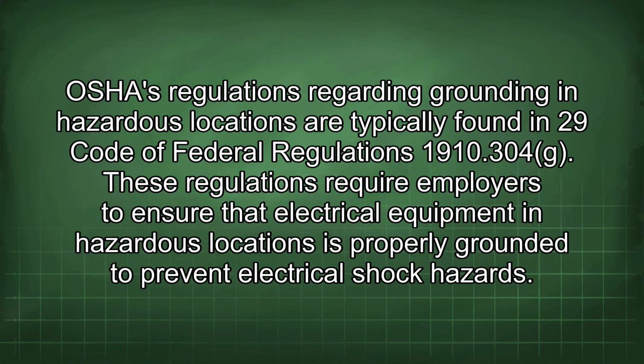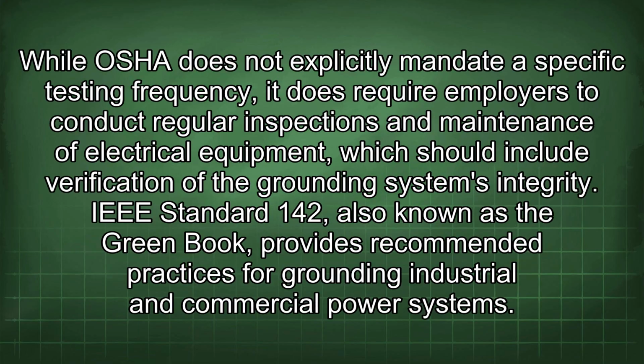OSHA's regulations regarding grounding in hazardous locations are typically found in 29 Code of Federal Regulations 1910.304. These regulations require employers to ensure that electrical equipment in hazardous locations is properly grounded to prevent electrical shock hazards. While OSHA does not explicitly mandate a specific testing frequency, it does require employers to conduct regular inspections and maintenance of electrical equipment, which should include verification of the grounding system's integrity.